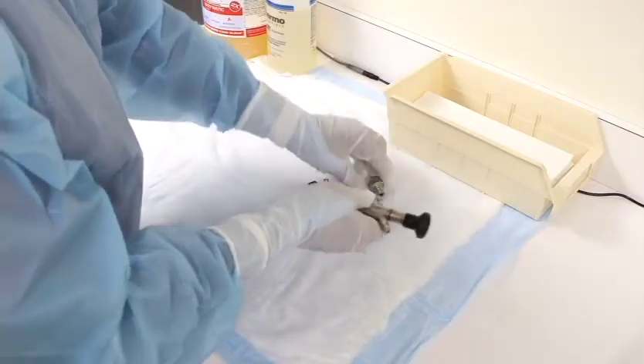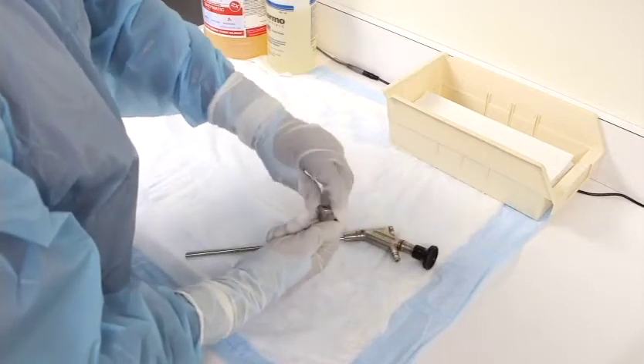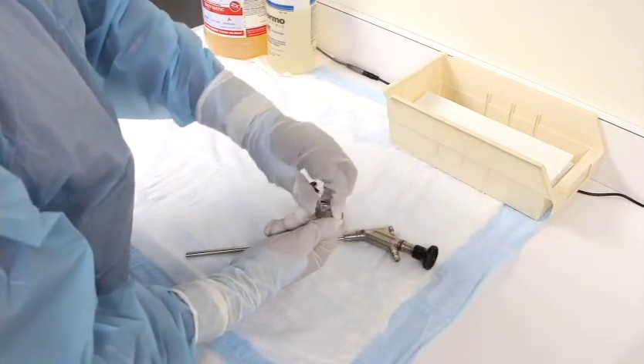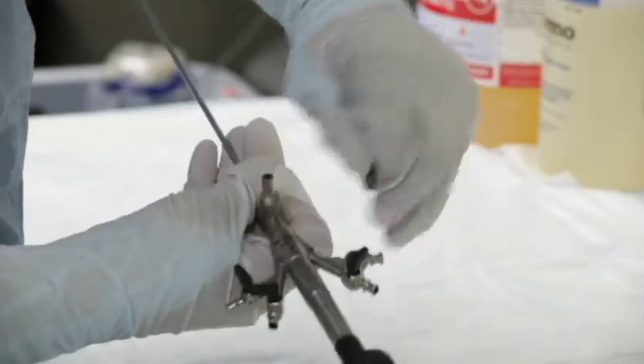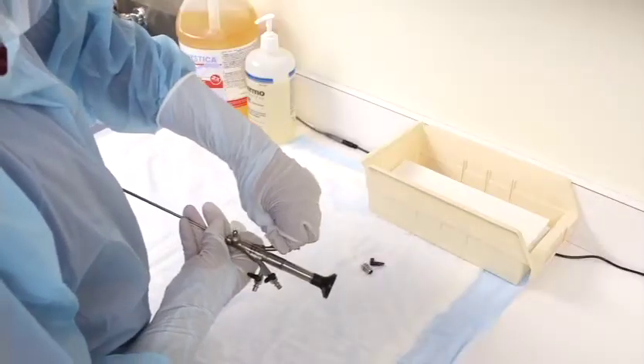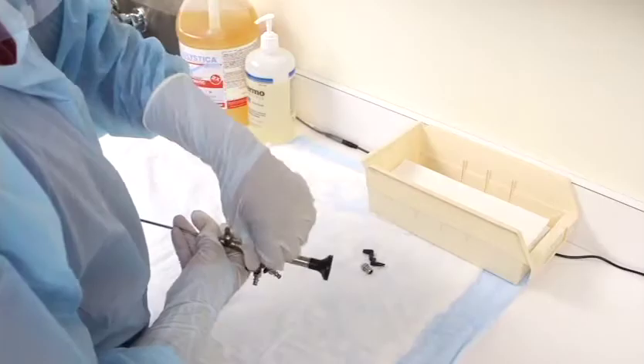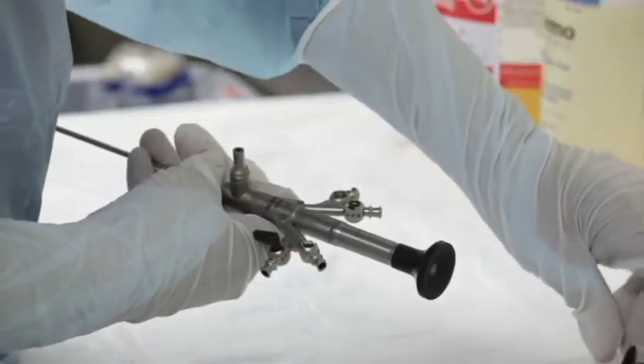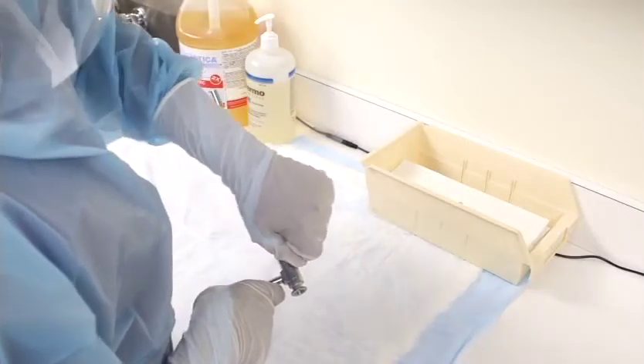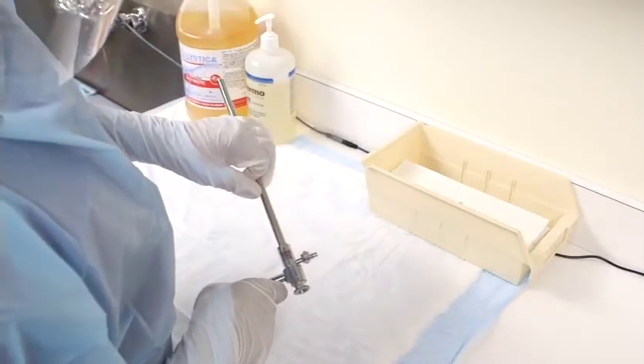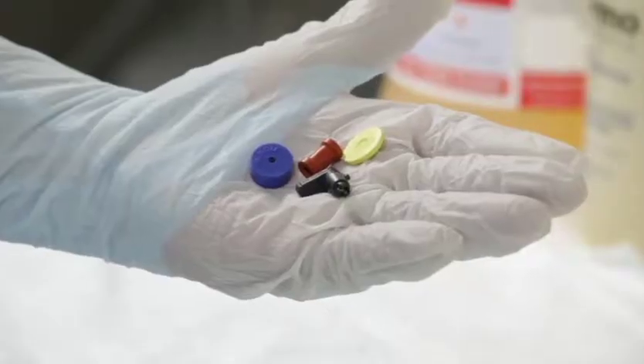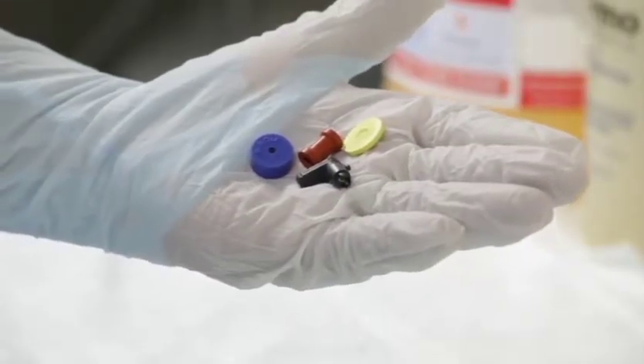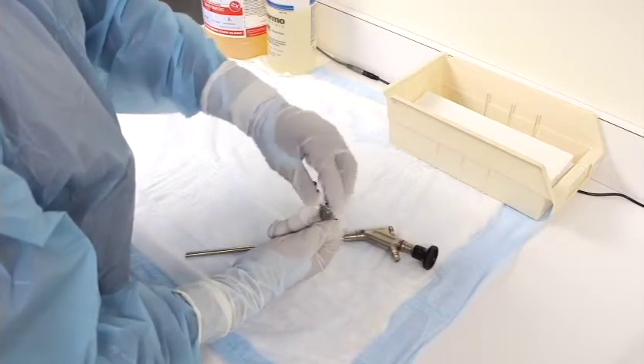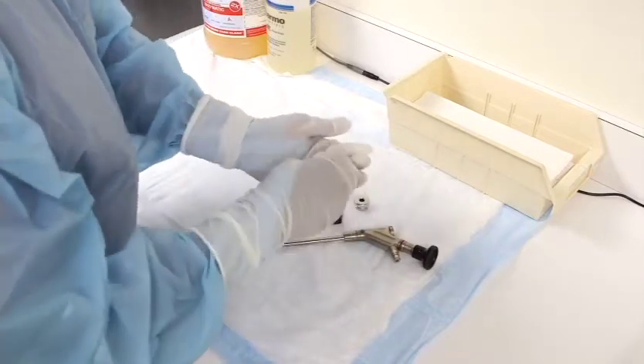Next, remove any adapters, sealing membranes, sealing caps, and stopcocks from the channel ports of the endoscope. Stopcocks may be metal or black plastic. Black plastic stopcocks are removed after each use to clean the ports. Replace with new stopcocks when they don't fit tightly into the stopcock housing. Metal stopcocks are usually not removable and must be in the open position to properly clean the ports. These removable membranes, stopcocks, caps, and adapters help prevent fluids leaking from the endoscope during a surgical procedure and are crucial to the endoscope's functionality.